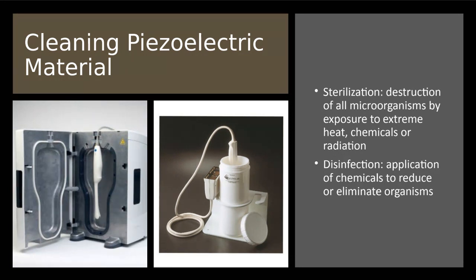We're also not using transducers invasively, meaning in surgical processes, without taking steps to protect the transducer and also the patient. So what we're doing mainly with some of our more sensitive transducers, like the transvaginal probe or the transrectal probe, is putting them in high levels of disinfection. You may have seen this at your clinic site. This is Cidex solution. This chemical solution that you are putting the probe in is a very high level of killing all types of organisms.